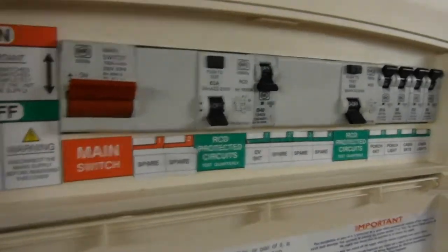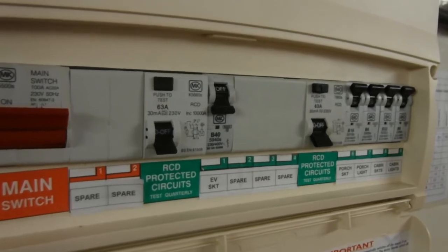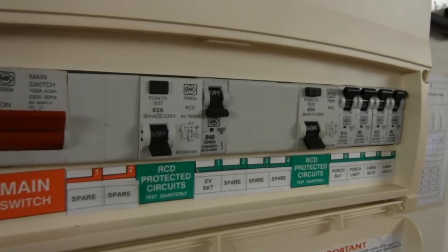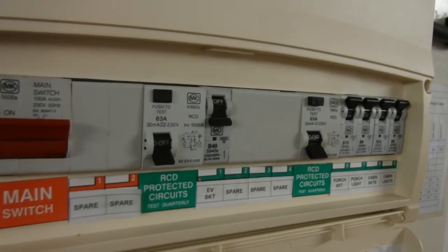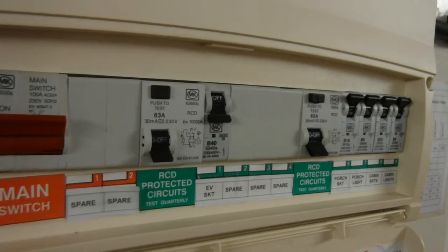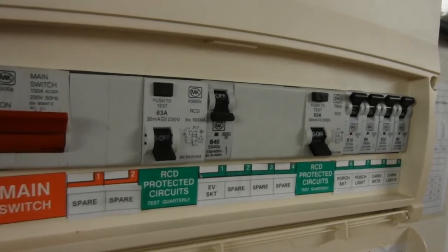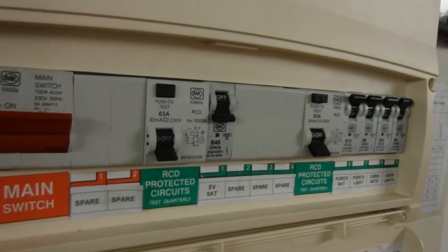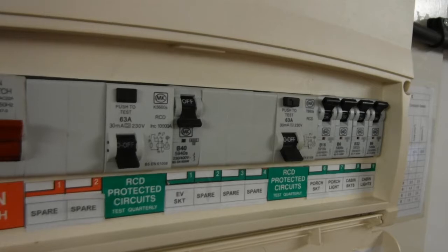Now we're moving to our ZS's. ZS can be obtained by two methods. It can be obtained by the dead method using two measured values, that is the R1, R2 value obtained at continuity and then the ZE value, and that gives you a calculated ZS, and it's super safe by doing that method.